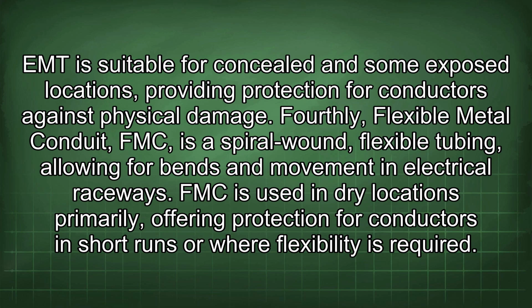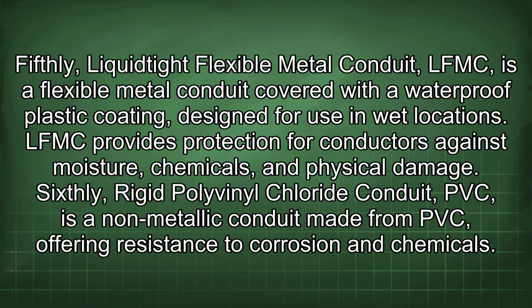Fourthly, flexible metal conduit, FMC, is a spiral wound, flexible tubing, allowing for bends and movement in electrical raceways. FMC is used in dry locations primarily, offering protection for conductors in short runs or where flexibility is required. Fifthly, liquid-tight flexible metal conduit, LFMC, is a flexible metal conduit covered with a waterproof plastic coating, designed for use in wet locations. LFMC provides protection for conductors against moisture, chemicals, and physical damage.